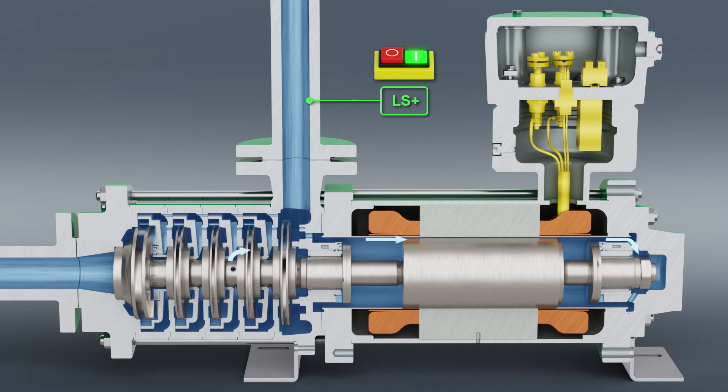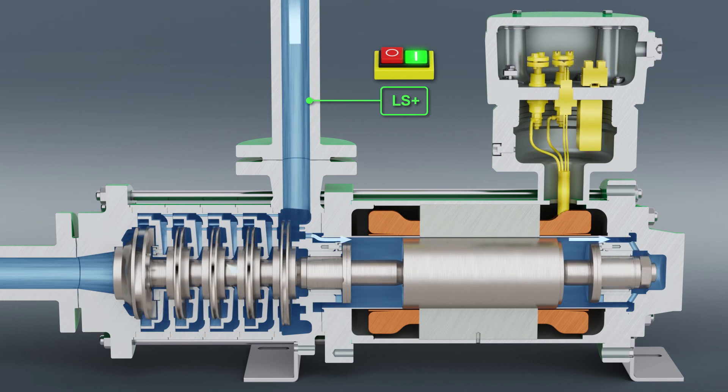At higher differential pressures, the Multi-Stage design works at better efficiency and lower NPSH value. Liquid cooled canned motors are low noise and low vibration centrifugal pumps and offer double protection against leakage.